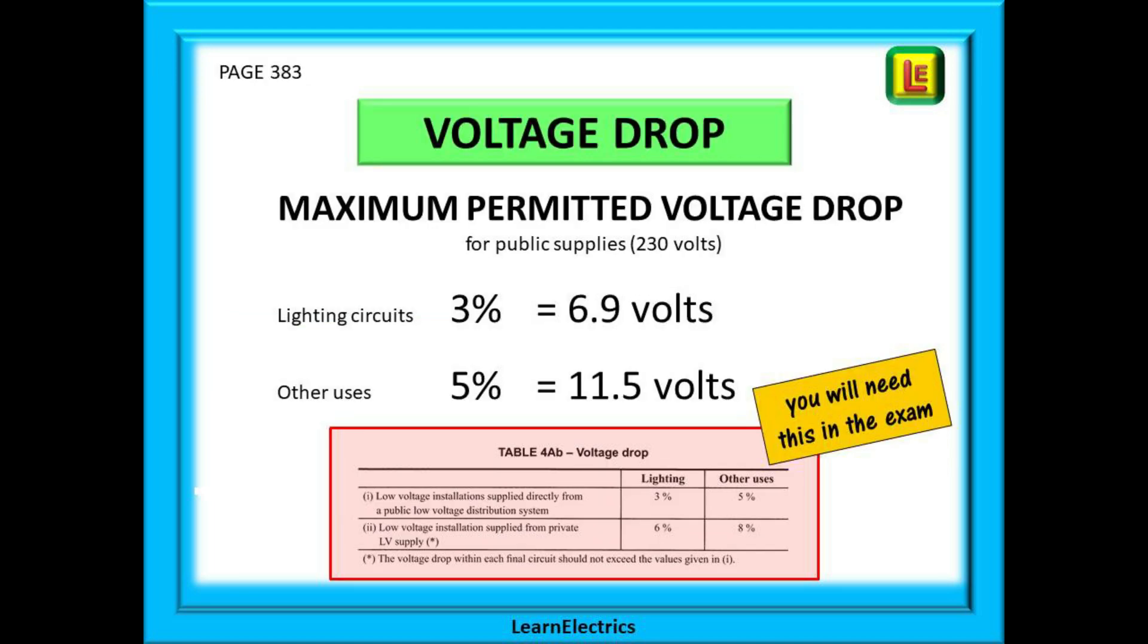Voltage drop is another favorite calculation for exam setters. First of all we need to know what is the maximum permitted voltage drop for a public supply at 230 volts such as we have in the UK. On page 383 we will find table 4AB. This tells us that for lighting circuits the voltage losses in the actual conductor should not exceed 3% of 230 volts which is 6.9 volts maximum. And for all other circuits the maximum is 5% or 11.5 volts.